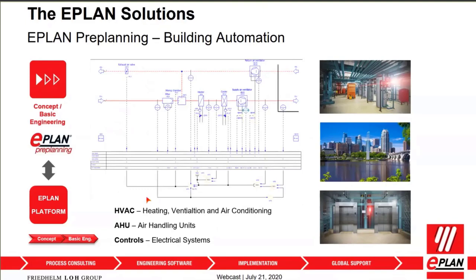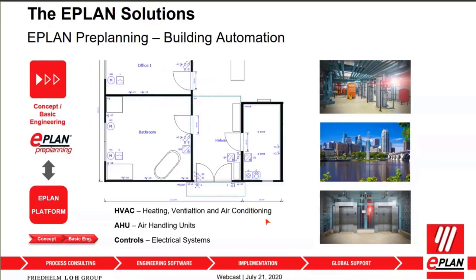A drawing from a design perspective can capture all your sensors, measuring devices, filters, fans, ventilators, and air conditioning systems cooling and heating incoming air, identifying the control system needed. You can also use architectural layouts — with tools like AutoCAD or Autodesk Revit, you can export information from Revit in Excel format and import that data into ePlan to identify all control systems and start planning wiring diagrams and control panels.